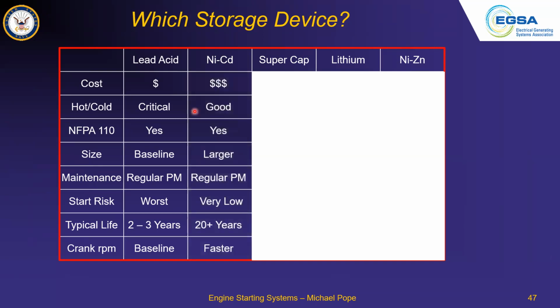Okay, the NiCad battery. Cost is much more. Hot and cold is really good. NFPA, it does meet that, as does the lead acid. And part of that specification, I believe, calls for the starting system to have the capability of providing 3 separate starts with like a 15-second separation between the start attempts. So those 2 batteries will do that.